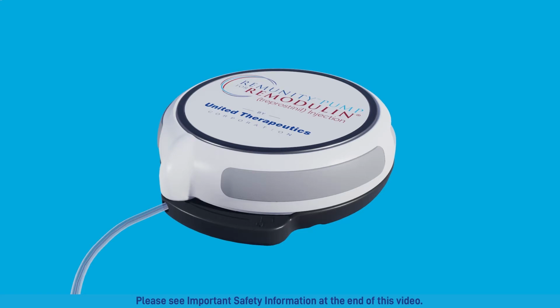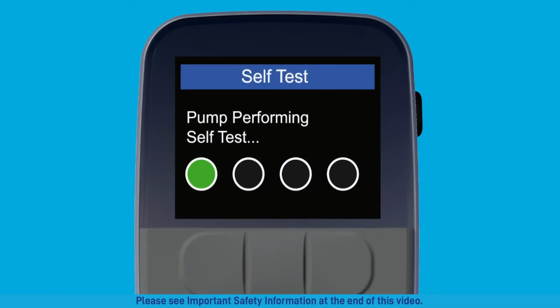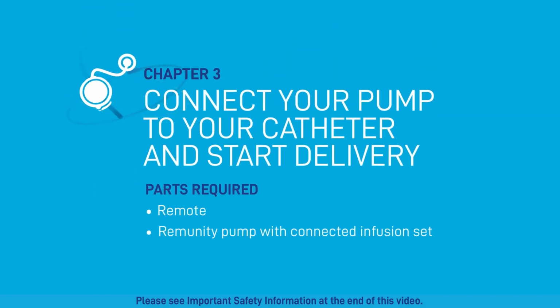You should hear a series of beeps coming from the pump, followed by one last confirmation beep. A self-test will display on the remote. Do not connect the infusion set tubing to your inserted catheter until the self-test is complete. Once the pump's self-test is complete, you will connect your pump to your catheter and start delivery.